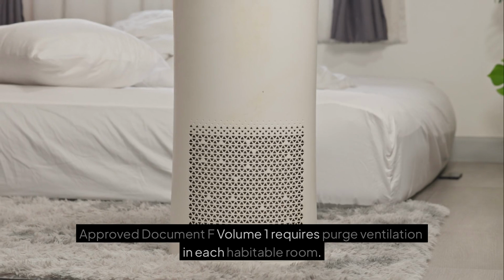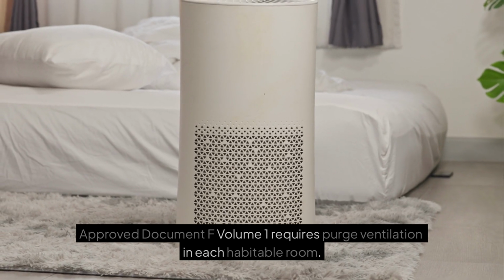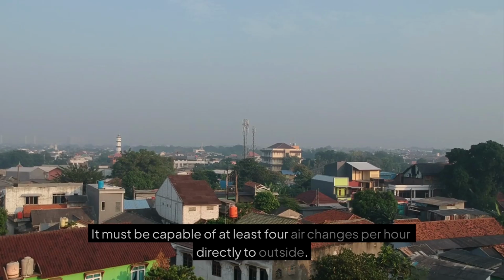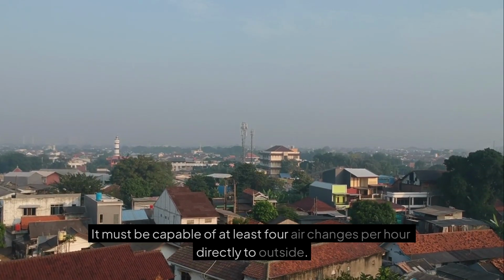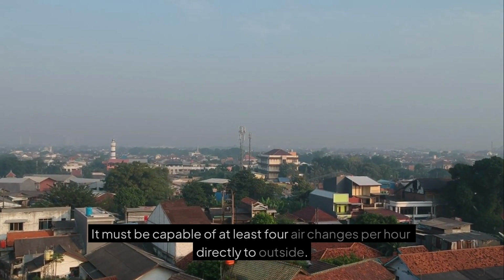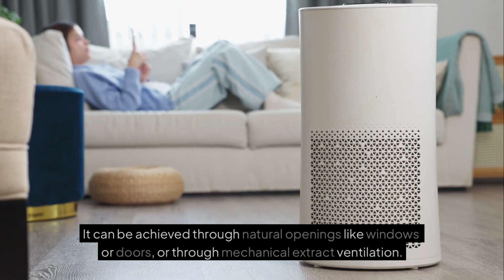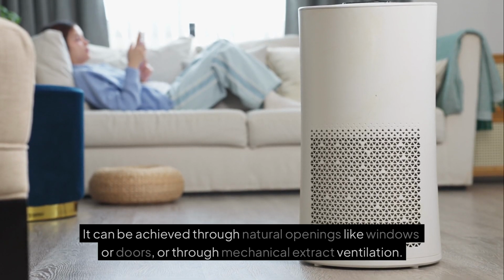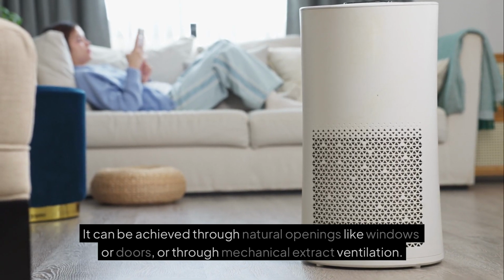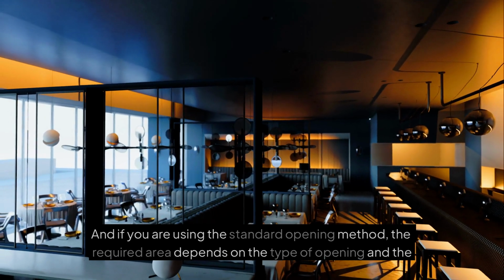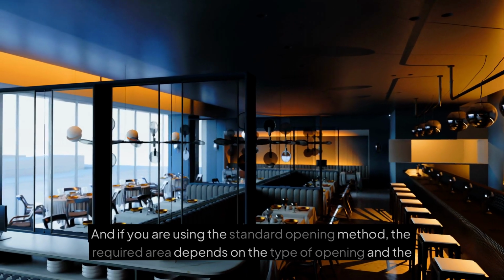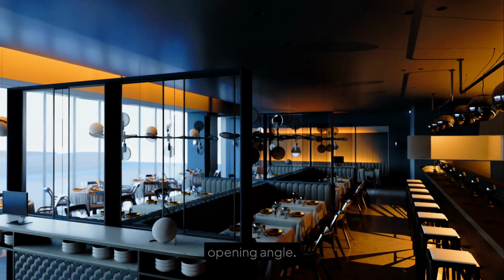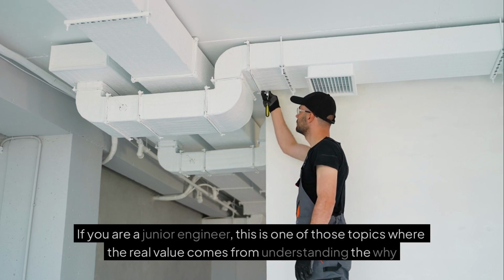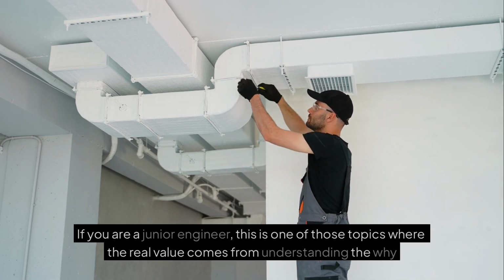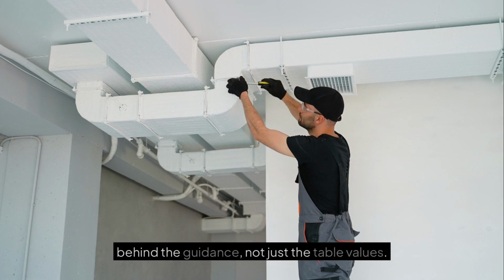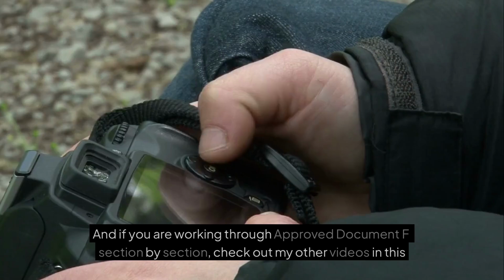So to summarize, Approved Document F Volume 1 requires purge ventilation in each habitable room. It must be capable of at least 4 air changes per hour directly to outside. It can be achieved through natural openings like windows or doors, or through mechanical extract ventilation. And if you are using the standard opening method, the required area depends on the type of opening and the opening angle. If you are a junior engineer, this is one of those topics where the real value comes from understanding the why behind the guidance, not just the table values.